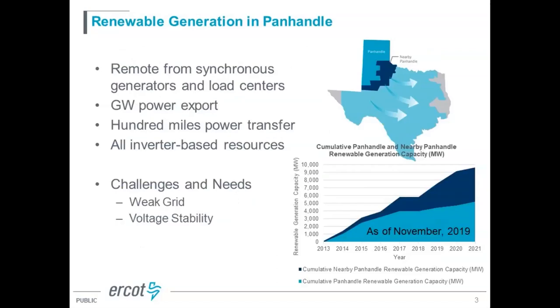Another high-level piece of background is that the application we considered for synchronous condensers is in the area we call the Panhandle region in ERCOT. There are unique characteristics of this region in West Texas, in the corner of ERCOT. To summarize, the Panhandle is really a remote area, remote from the synchronous generators and the load centers in the ERCOT footprint.